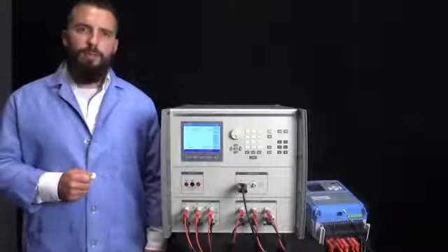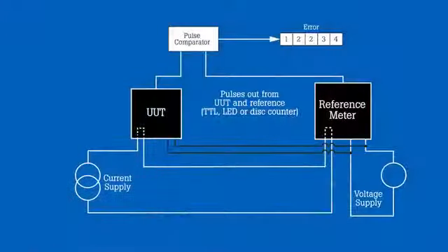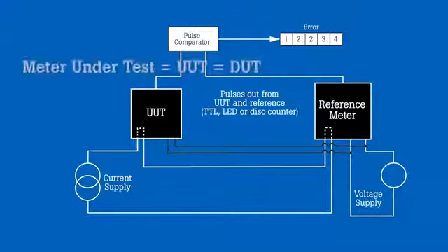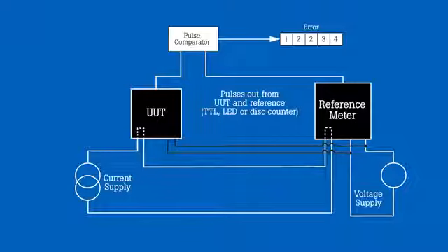Calibrations are traditionally performed using a reference measurement technique where a known amount of energy is simultaneously supplied to a reference meter and the meter under test. A reading from the reference meter is then compared to a reading from the UUT and the error is calculated. Three separate pieces of calibration equipment are required to complete this task.